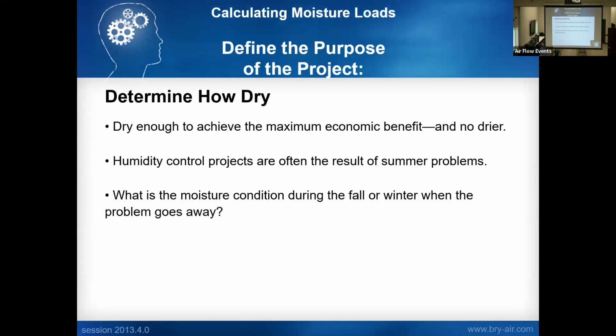So again, when you're determining how dry you want to dry, we build units down to controlled space minus 50, 60 dew point, delivered air minus 80 to minus 96 dew point. So we can provide a lot of dry air. If you need 20% RH, you don't need me to deliver air at minus 40 dew point to your space. So again, it's understanding the loads and understanding you don't want to over dry because you pay for it. The bigger the equipment, the higher the cost and the more energy.